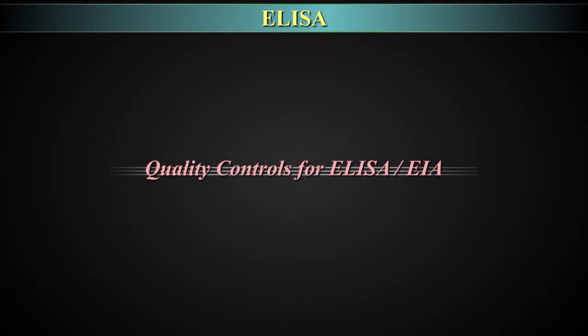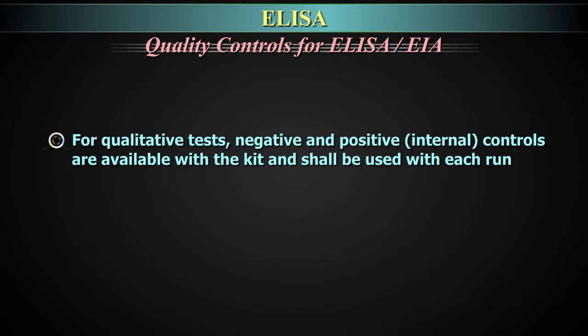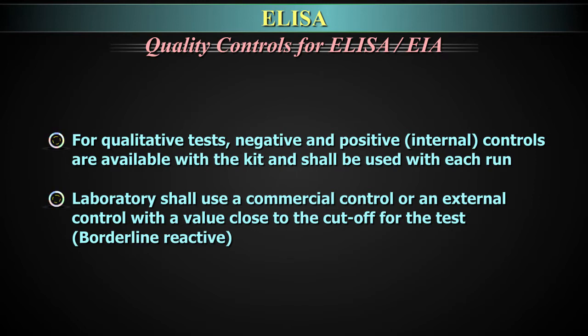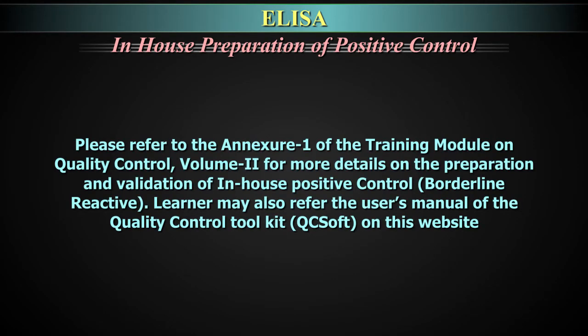Quality controls for ELISA. For qualitative tests, negative and positive internal controls are available with the kit and shall be used with each run. In addition, laboratories shall use a commercial control or an external control with a value close to the cut-off for the test — borderline reactive. In-house preparation of a positive control, i.e. borderline reactive and external to the kit, is also possible. Please refer to Annexure 1 of the Training Module on Quality Control, Volume 2, for more details on the preparation and validation of in-house positive control where it is borderline reactive. The learner may also refer to the User's Manual of the Quality Control Toolkit, QCSoft, on this website.